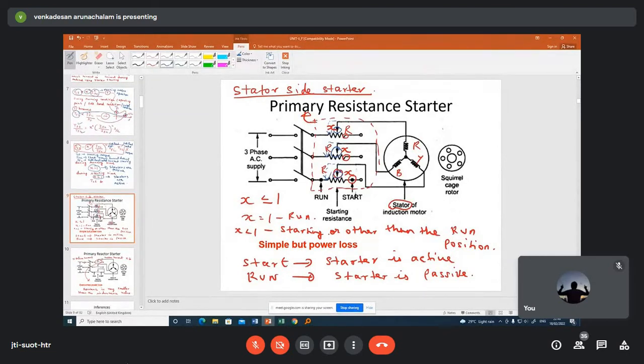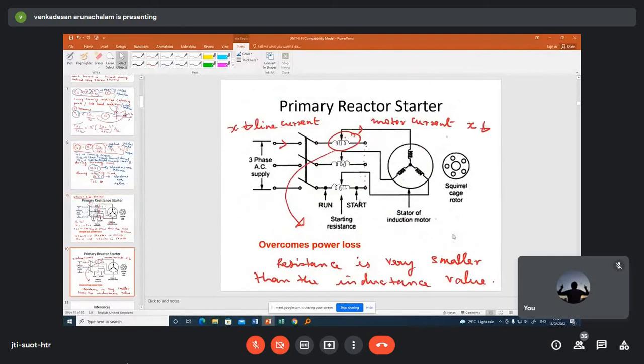reduction in the efficiency. In order to overcome this problem, in order to avoid this copper loss problem, people have replaced this resistance with inductance. So that is the primary reactor starter. The concept remains the same, similar to the stator resistance starter. But the power loss will be very much minimum when compared to the primary resistance starter.